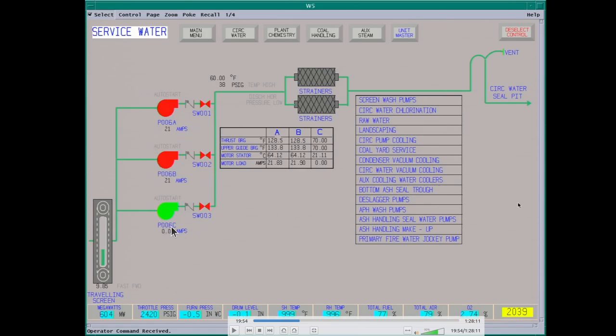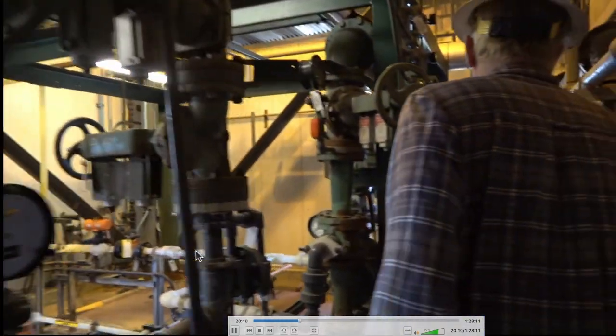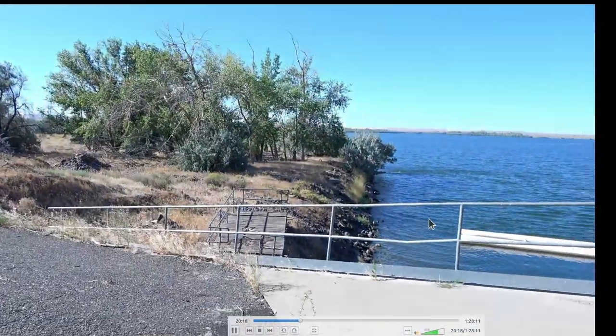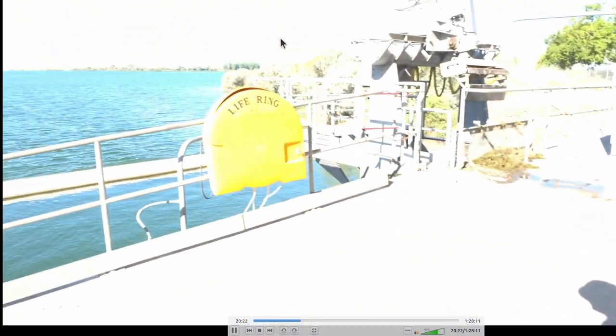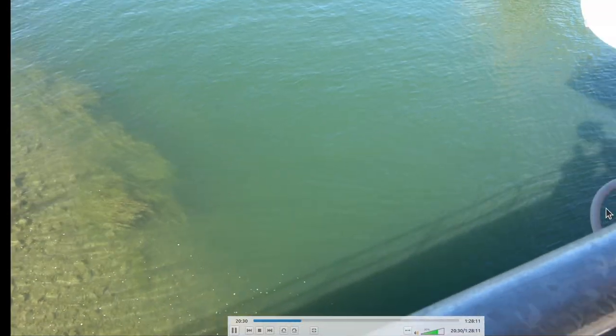Here's your service water — three pumps down the intake along with your two CIRC water pumps. It has a traveling screen. This is the water used to cool your aux cooling water exchangers. It runs screen wash pumps and a bunch of little items — basic plant water used for various processes. You lose this, you lose your aux cooling water and your oil is overheating — so it's pretty critical. This is inside the intake building. This is the chlorination system — you put a little bit of chlorine in the water so often to kill any clam growth in the surface condensers. Out here's the intake — you've got traveling screens to filter out any large debris, and also bar screens and rakes to pull out any tree limbs.